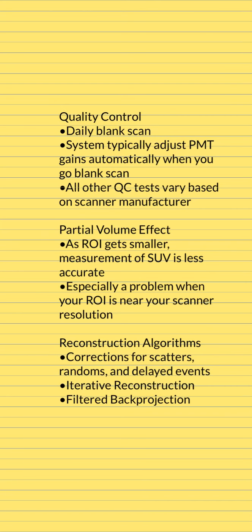It'll test that your energy resolution is correct. And to be quite honest, your system manufacturer, the technician or the engineer typically does most of these tests for you, because it's included in the contract. So it's good for you to know why they're doing the test.